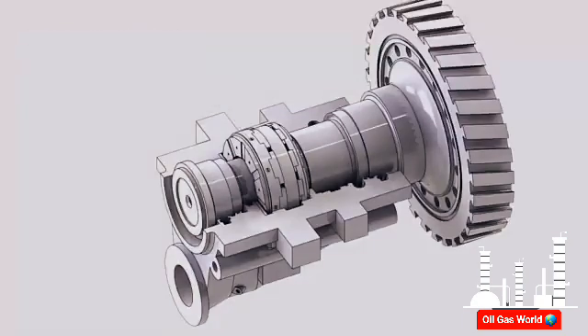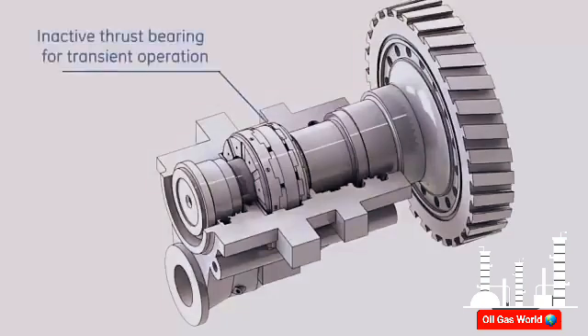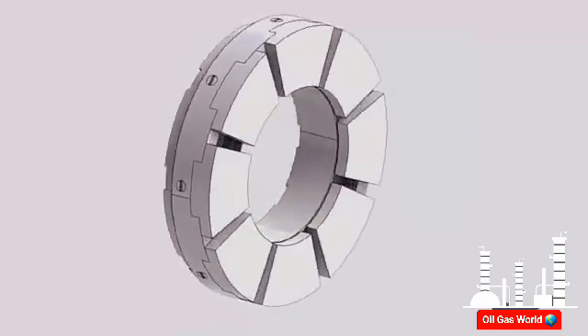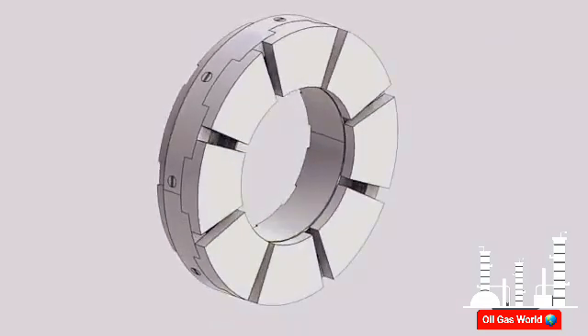While in transient operation during startup and shutdown, the shaft tends to move in the downstream direction, where the inactive or unloaded thrust bearing is located. The active thrust bearing is a tilting pad equalizing type bearing. An equalizing type bearing is capable of sustaining high axial loads and is tolerant of shaft and housing misalignment.